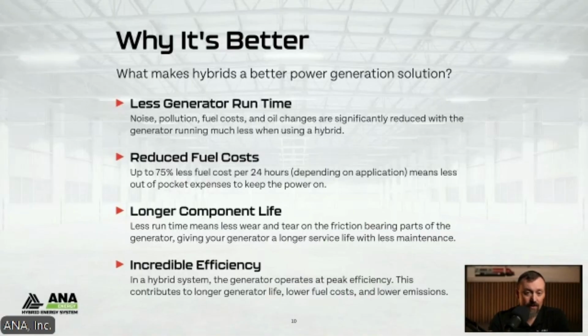So it's running up there at 70, 80, 90% of load in most cases, which is better for the engine. You have less tier 4 emissions issues from things like wet stacking or running underloaded. It really prevents that, so it increases efficiency as well as reliability.